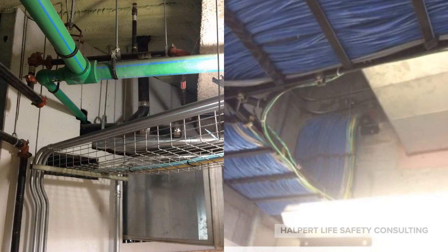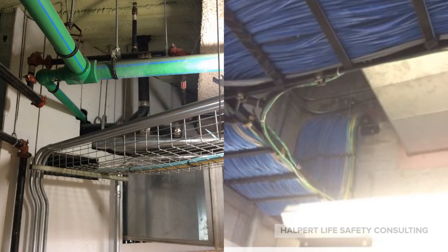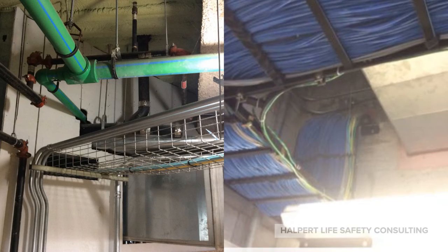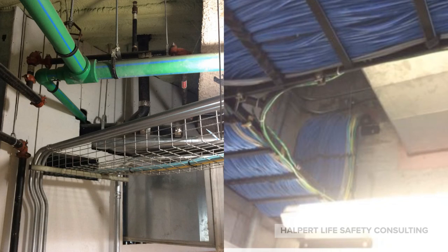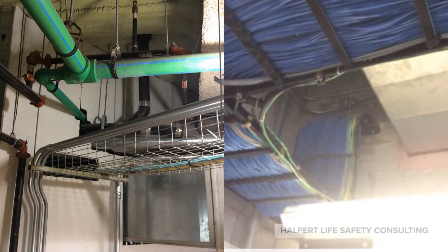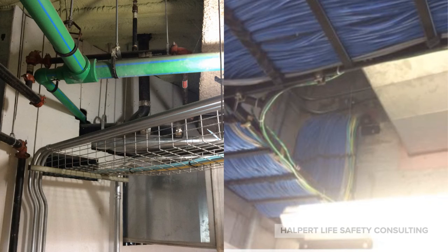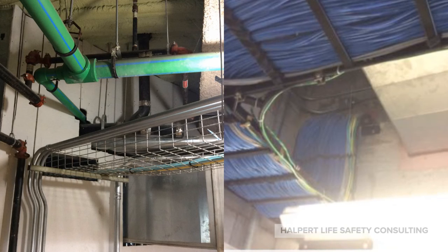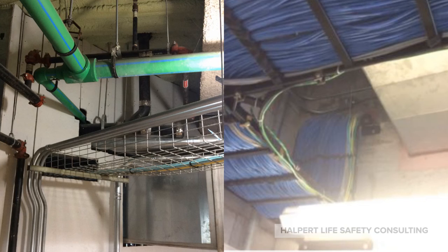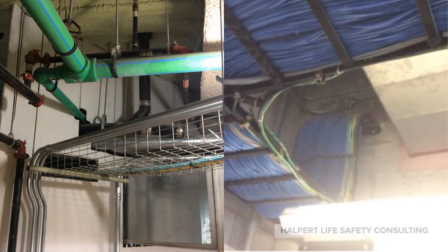Next up, we have cable trays. The one on the left is going through a gypsum wall, so that will be a WL detail, and the one on the right is a block wall, so that may be CAJ or WJ. The cable trays are in the 4000 series details, but I put both of the pictures up so that you can see the difference between a wire rack on the left and a ladder rack on the right.